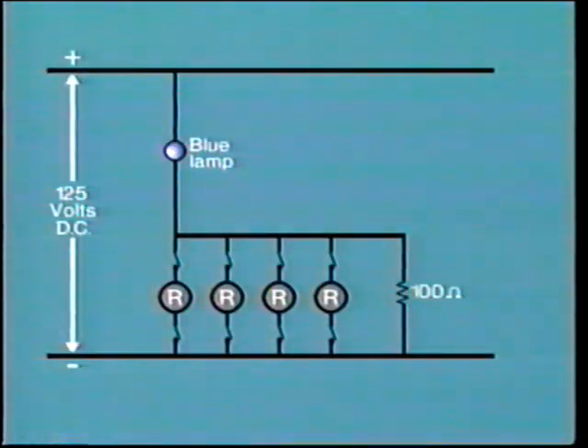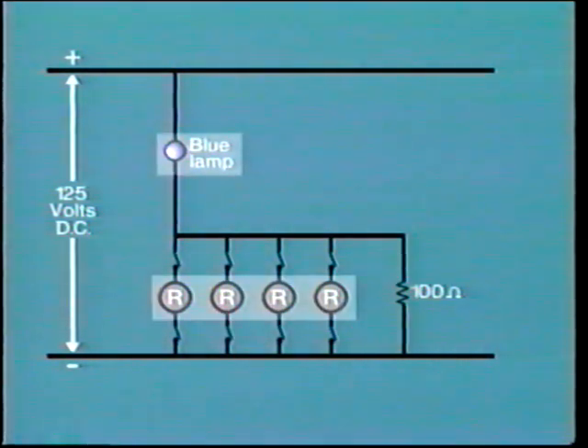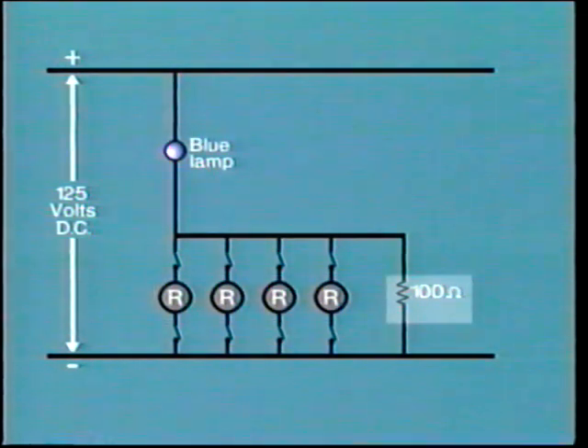One relay technician trying to resolve this problem elected first to disconnect the downstream auxiliary relay coils. He managed to disconnect 3 of the coils, but at that point the remaining coil operated and tripped the circuit. So how did this happen? Well, in this arrangement, we have one indicating lamp in series with these 4 coils in parallel. There is also a resistor across the coils. This resistor was found to be open-circuited.